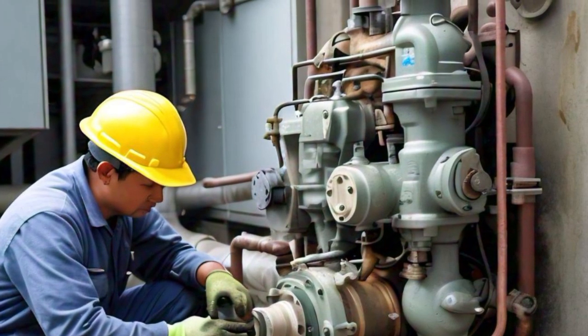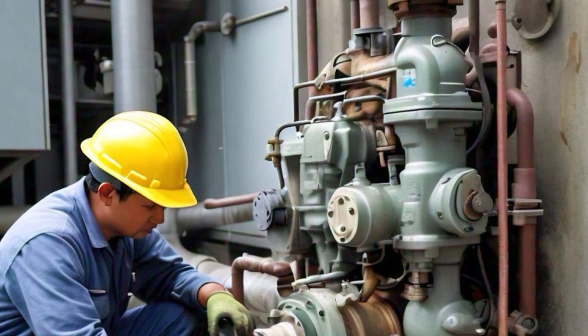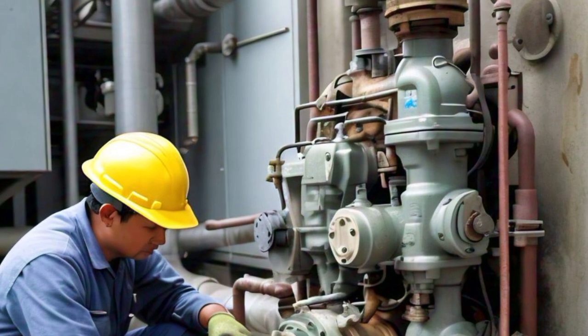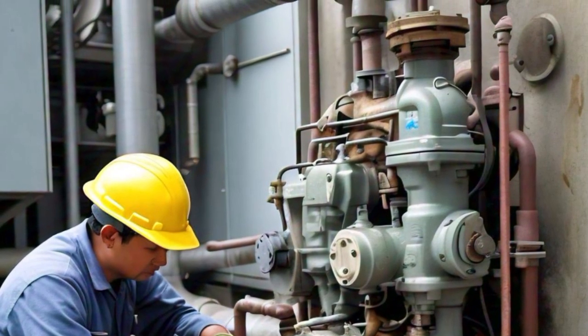8. Failure of the motor. In actuality, motor failure is the most frequent reason for pump failure. This happens when the motor itself overheats, usually due to insufficient cooling from the water flowing past the motor's outside.